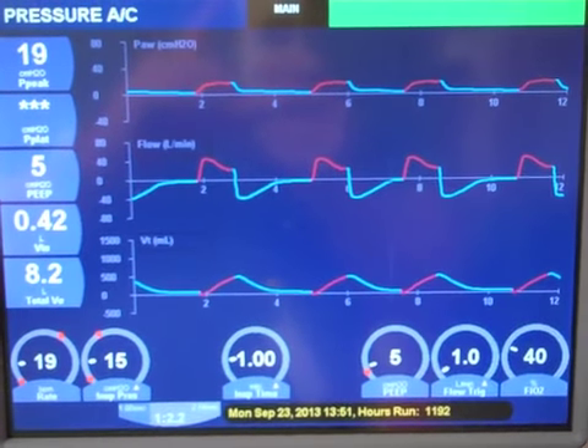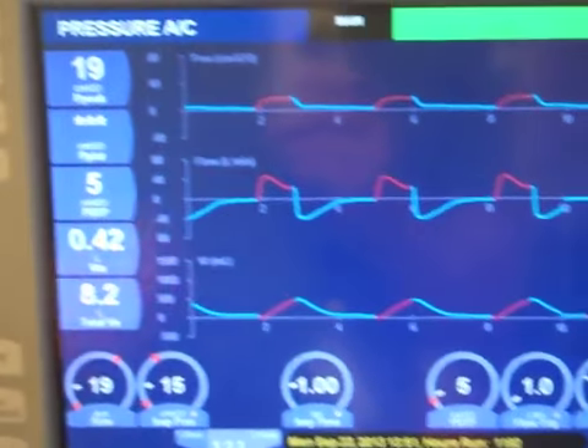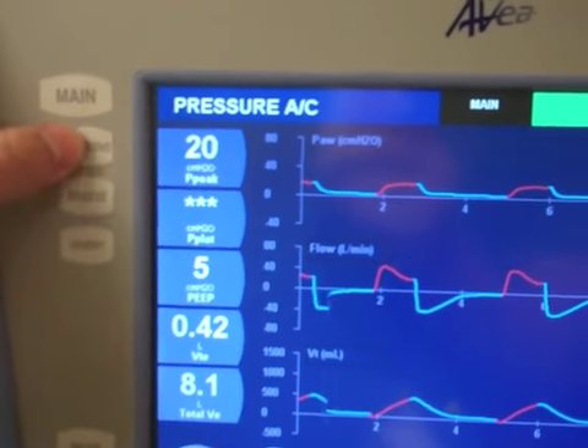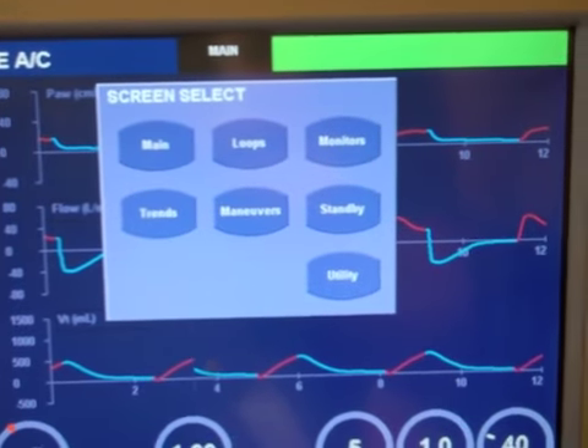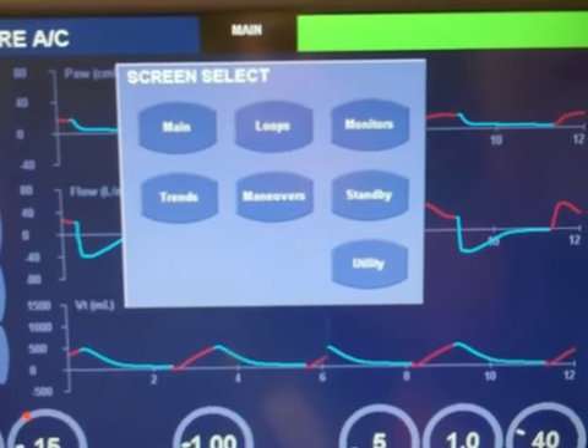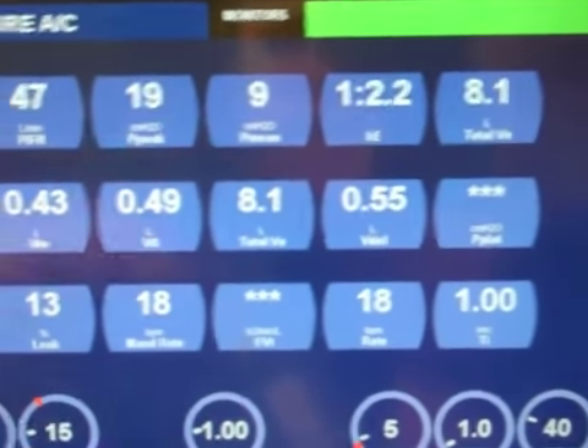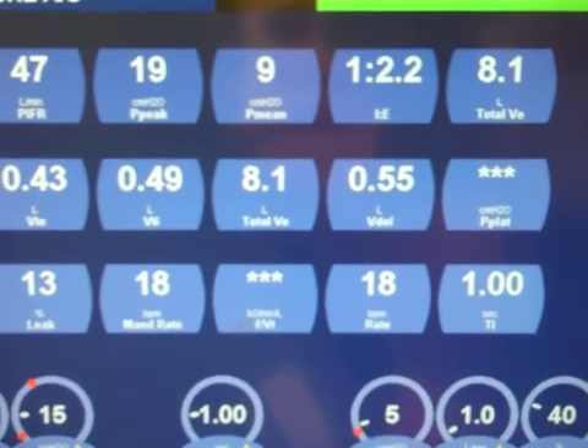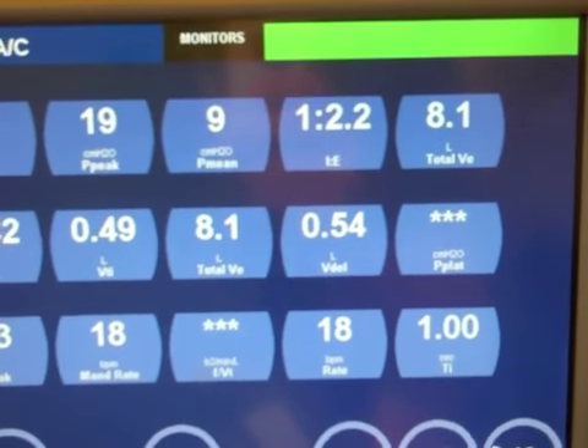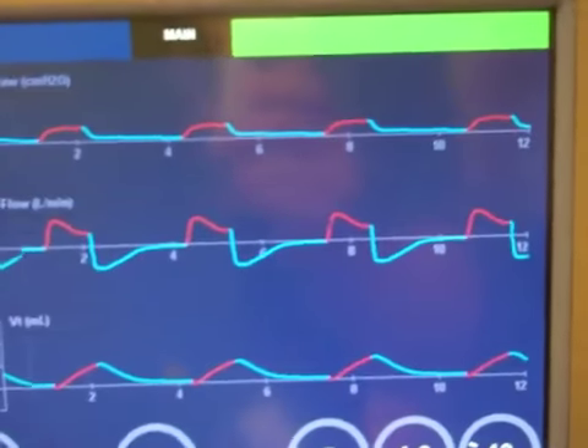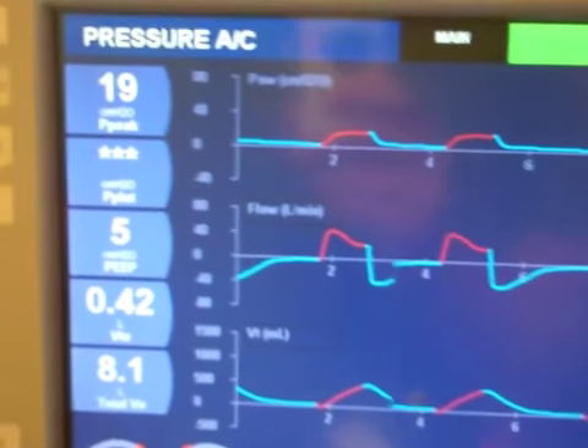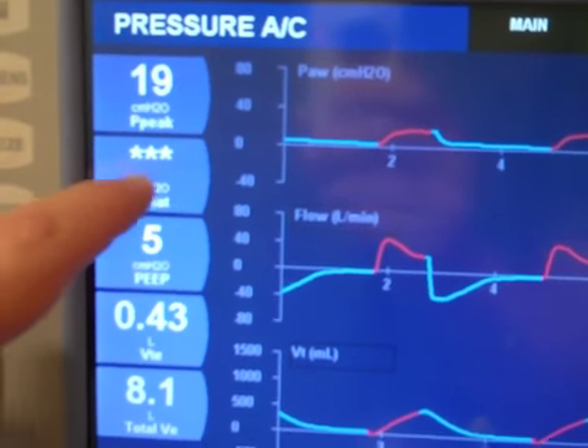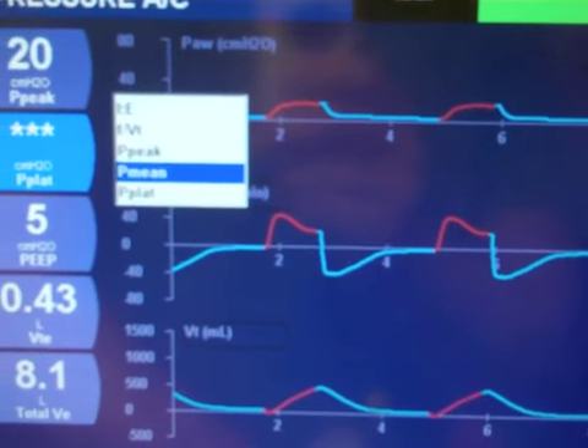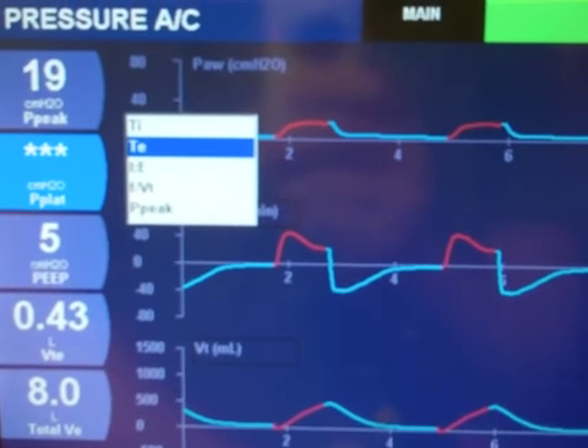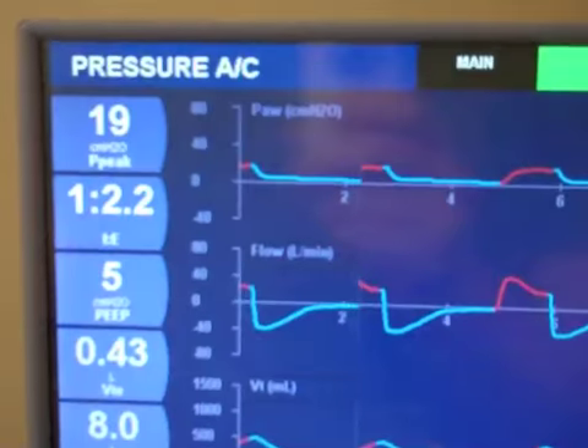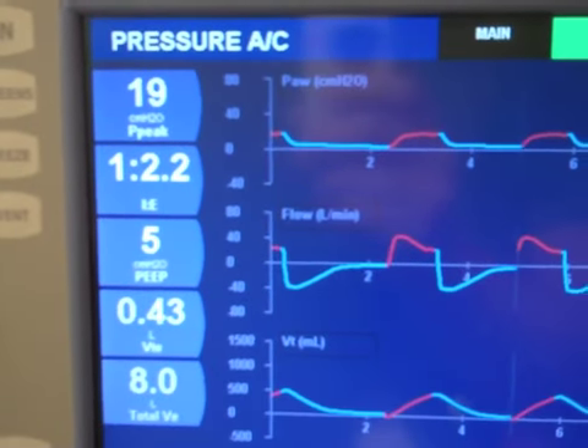So this is what the Avea graphics package looks like when you're ventilating. On the side there's a hard key here. If you hit screens, a little tab will come up, and you can actually choose to manipulate this as you will. So if you go into monitors, you can see all the parameters there, but again you lose the scalars in this instance. So if you go back into screens, let's say you wanted just to go to main, but you wanted to change one of your red parameters. So let's say I didn't really need to look at my plateau pressure. You can touch that simply by pressing on it and picking whatever you want. So let's say I want my IE ratio, and then reselecting, and you have your IE ratio now displayed for you.